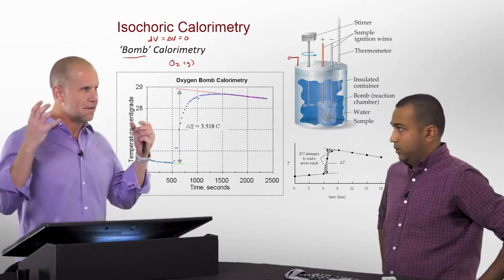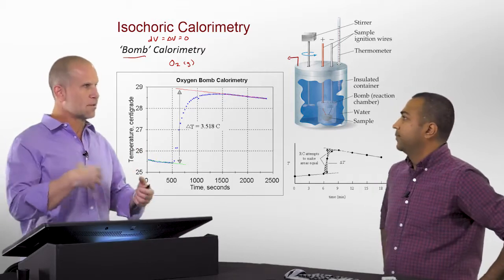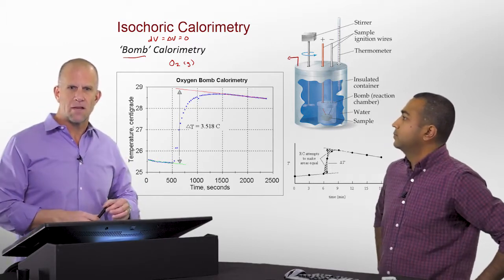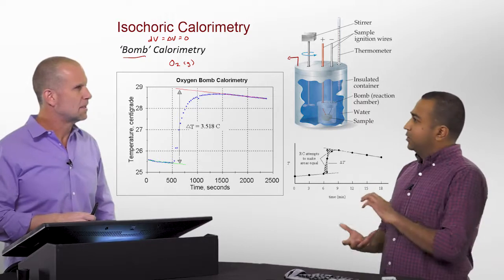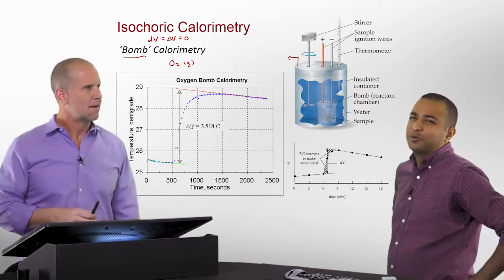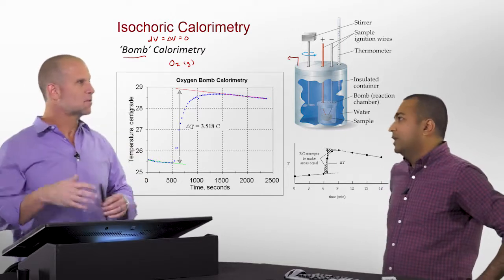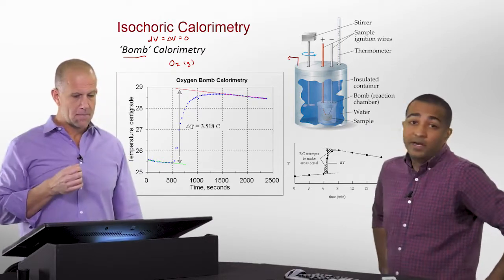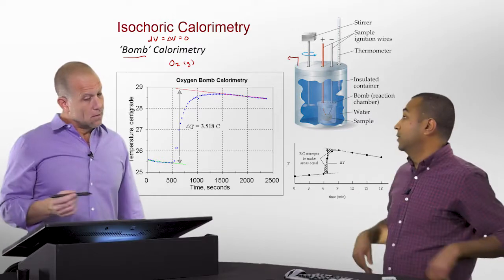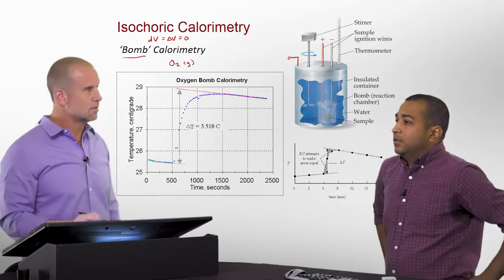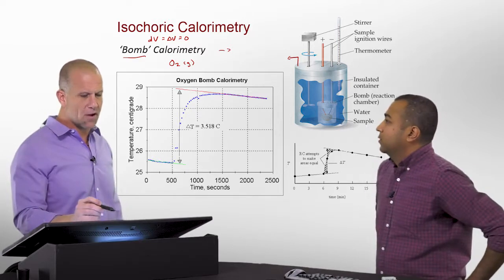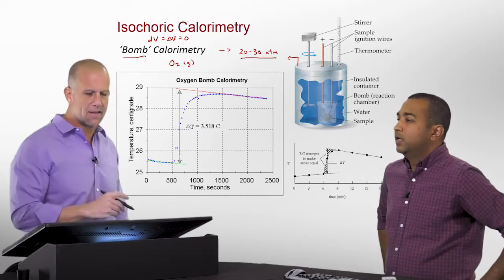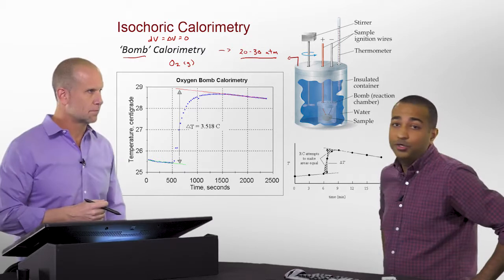In the bomb calorimeter, you put your sample inside a metal container — the bomb — and pressurize it with oxygen to about 20 to 30 atmospheres. You typically pelletize your material into a small pellet, put it in a little cup, and insert two wires that will heat the material and combust it once it's filled with oxygen. An electrical current is used to ignite the oxygen and do the combustion, and you make sure there is excess oxygen by purging out all other gases typically in air.